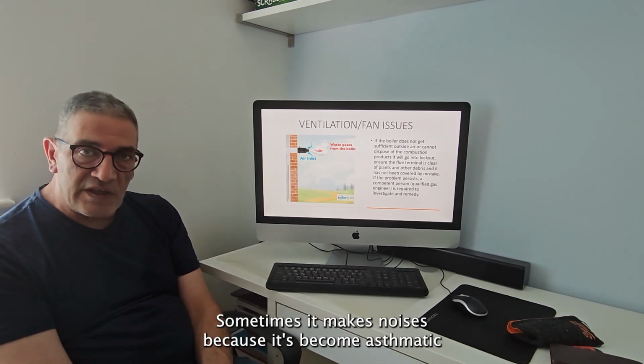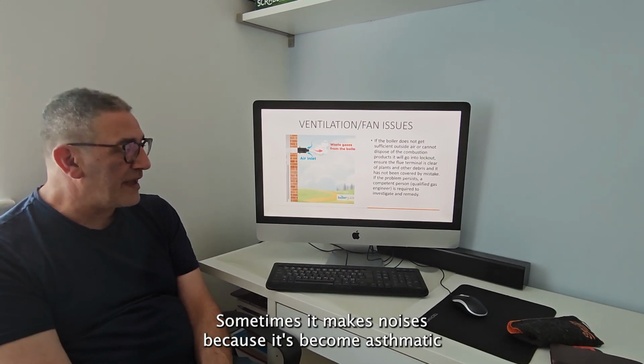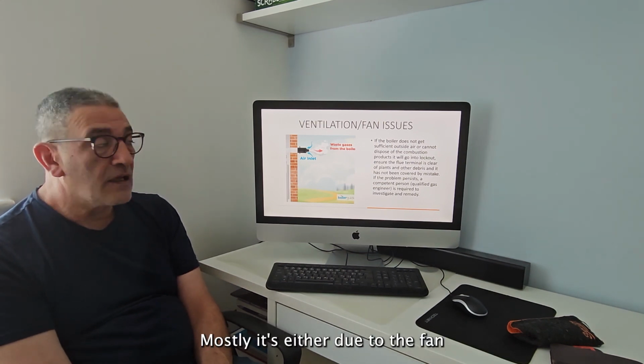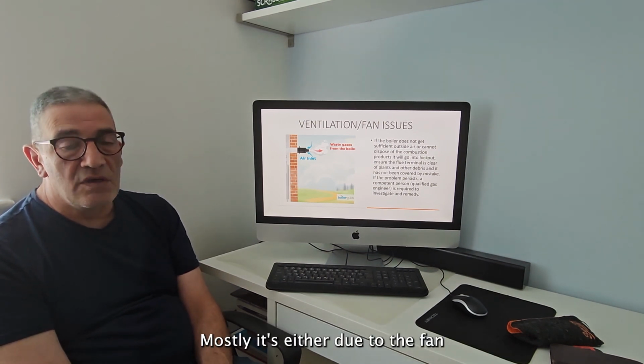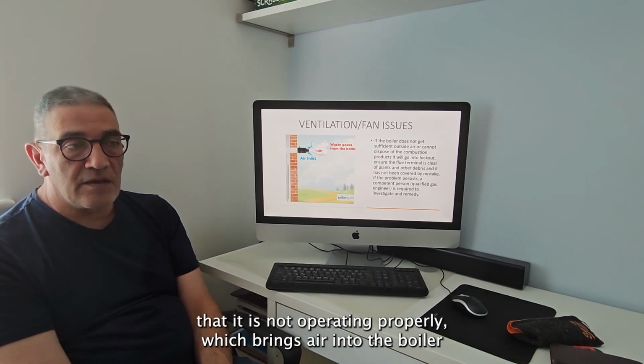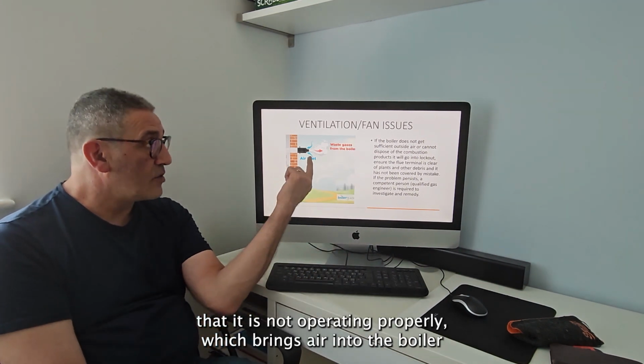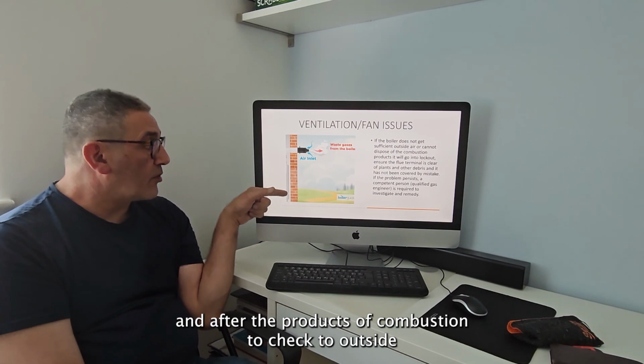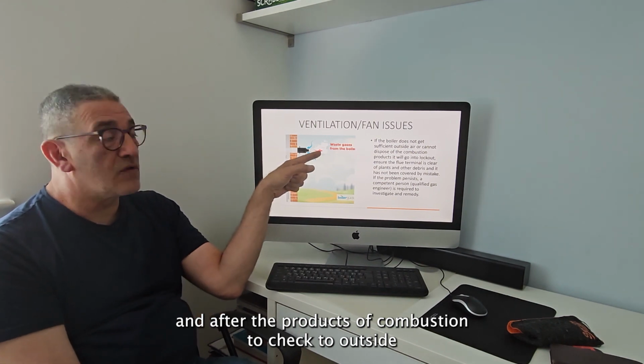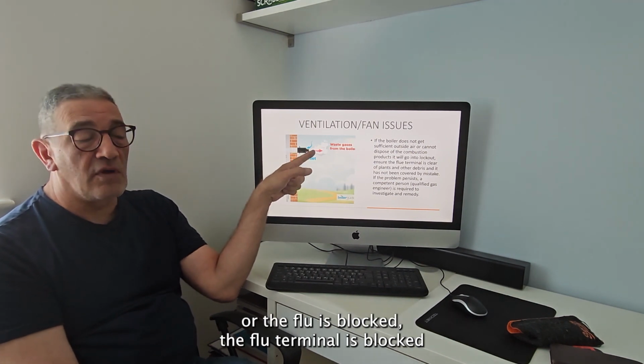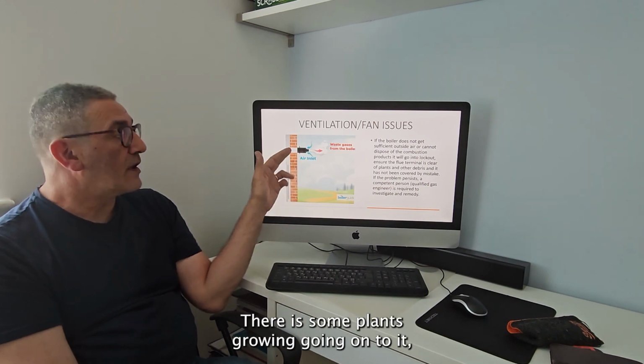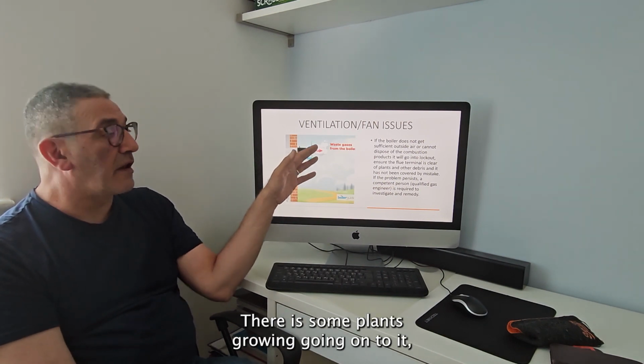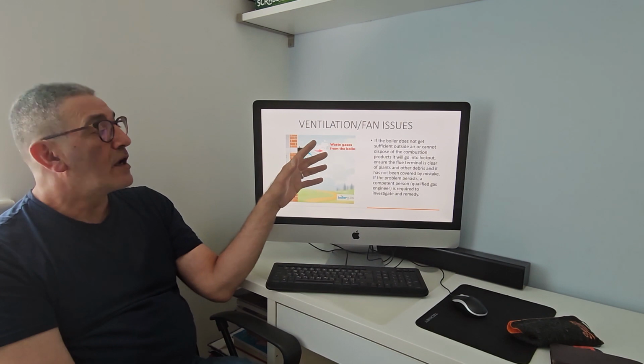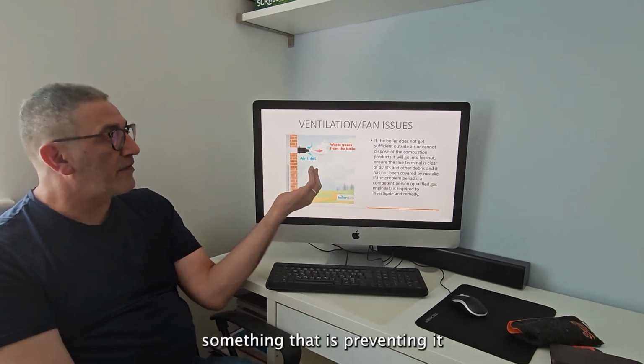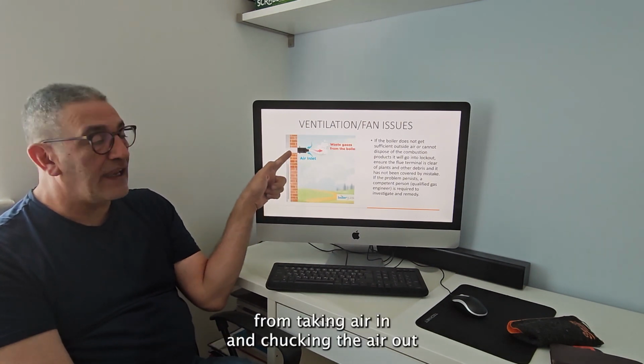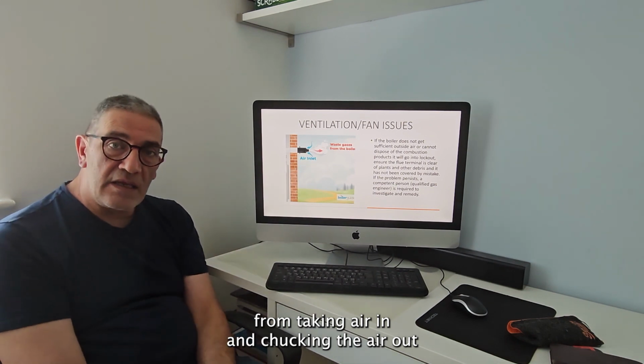Sometimes it makes noises because it has become asthmatic and it can't breathe properly. Mostly it's either due to the fan not operating properly, which brings air into the boiler and chucks the products of combustion to outside, or the flue is blocked. The flue terminal is blocked. There are some plants growing onto it, or something that is preventing it from taking air in and chucking the air out.